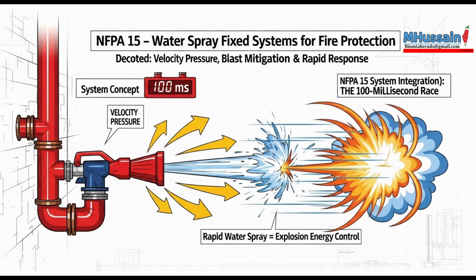And the integrity of those pipes relies heavily on the joints connecting them. If the design uses welding, Section 5.5.2.5 adds a step that engineers only familiar with NFPA 13 might miss: this pre-installation qualification. Yes, this is a critical difference from general practice. The welding procedure itself, not just the welder, must be prepared and qualified by the contractor or fabricator before any welding starts on site. Hold on, why qualify the procedure before the project even kicks off?